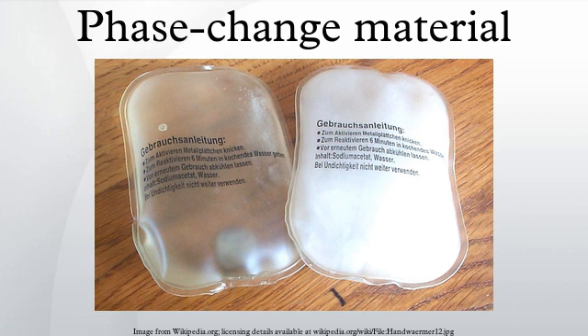When the ambient temperature around a liquid material falls, the PCM solidifies, releasing its stored latent heat. A large number of PCMs are available in any required temperature range from -5 up to 190 degrees Celsius. Within the human comfort range between 20-30 degrees Celsius, some PCMs are very effective. They store 5 to 14 times more heat per unit volume than conventional storage materials such as water, masonry or rock.